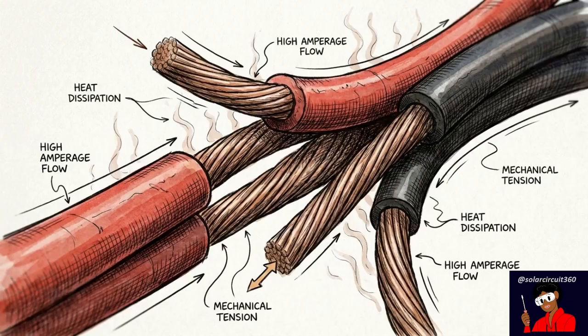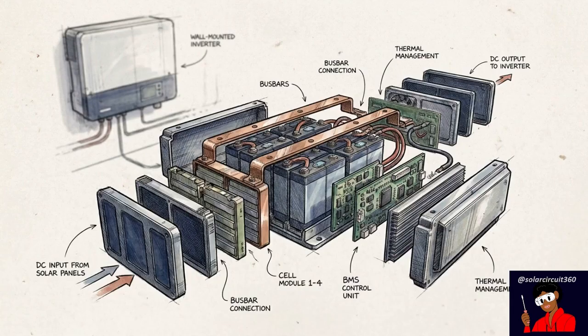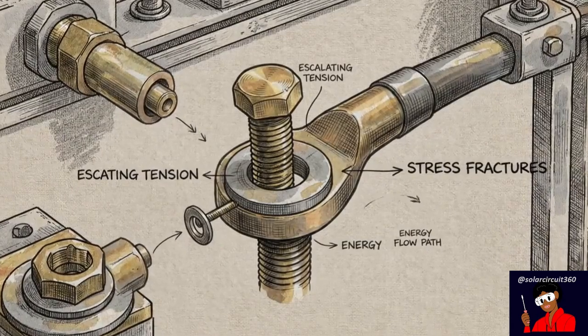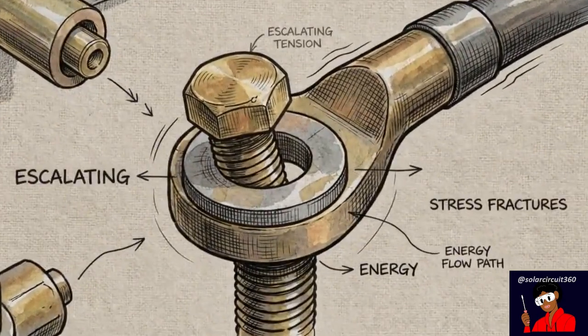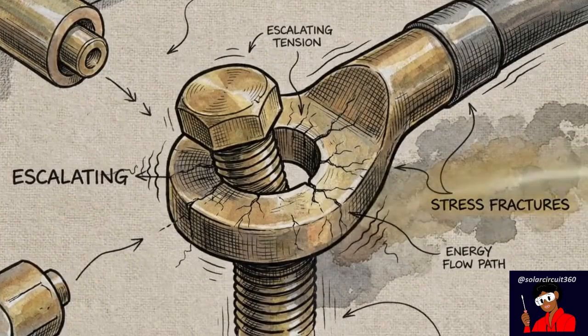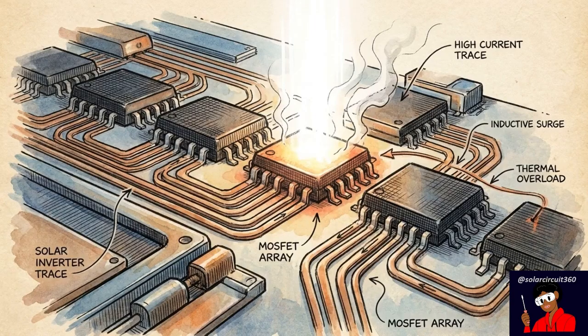This vacuum places intense physical stress on the DC cables bridging the battery bank and the inverter. The shift from a localized AC motor problem to a system-wide DC supply crisis occurs in fractions of a second. The inverter is just a middleman. The actual heavy lifting during a surge depends entirely on your DC energy reserves. A motor's mechanical startup resistance directly translates into a systemic DC power vacuum, exposing any weak link in your battery supply chain. In the precise millisecond that DC power vacuum hits, the system components are forced to evaluate whether they can survive the surge. If they cannot, the system shuts down.